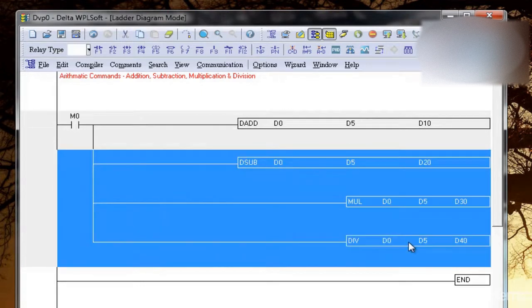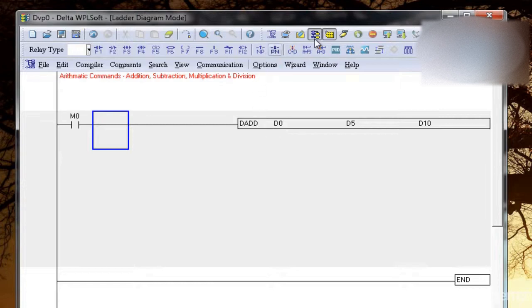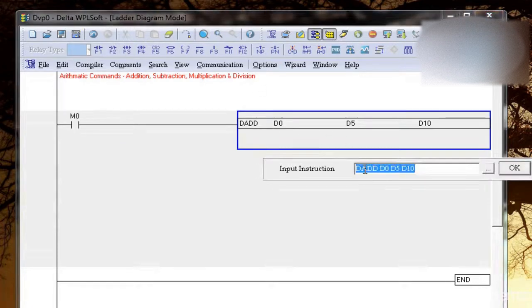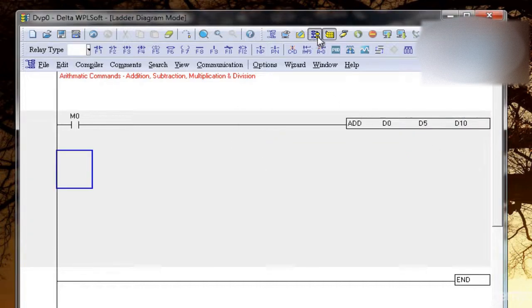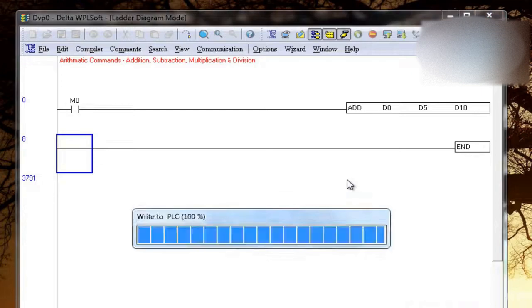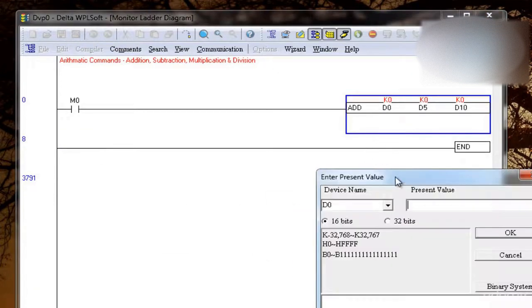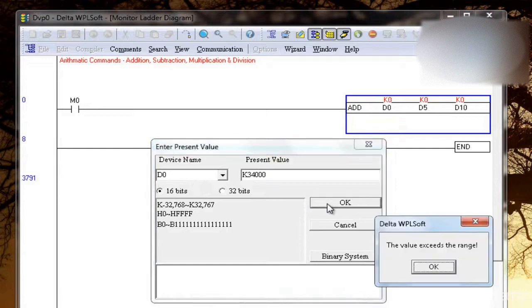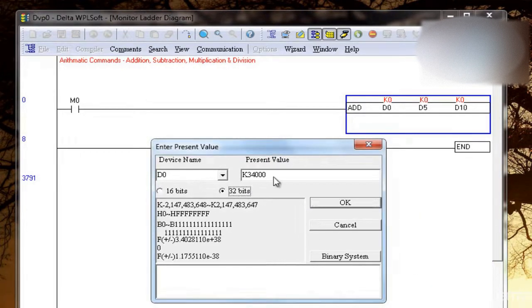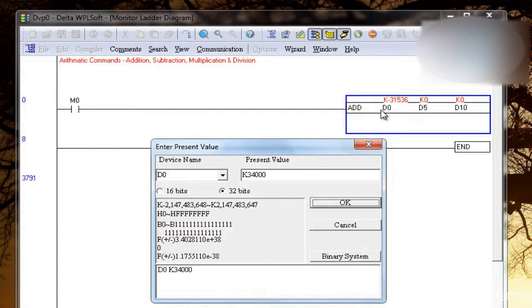If you want to take an example, let's try that. I'll use this add example and first let's try that without double. So let's just add two values in the data register and let's see the result. So this D0, I'll take K34,000. Now it says value exceeds the range. So I'll use 32 bit. So you see this value is 34,000 but here I'm getting minus 31536 because I haven't used D here.